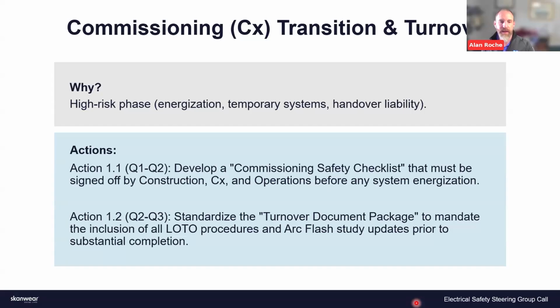The risks happen when the operators aren't there witnessing the system testing, and the emergency procedures aren't rehearsed beforehand. So what good looks like is the commissioning agent is going to say, we're about to go test this chiller, and the ops team is right there with them in tow. They're watching the plant get up to its full load, recording and documenting the numbers they're seeing - the pressures, temperatures - and documenting all that.